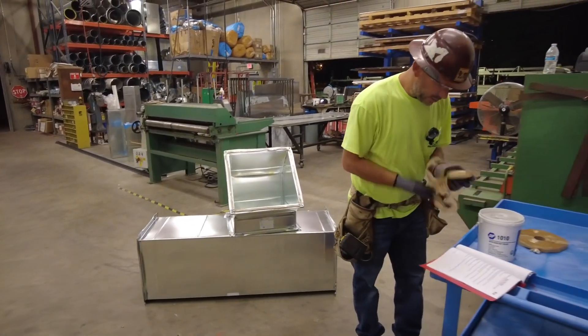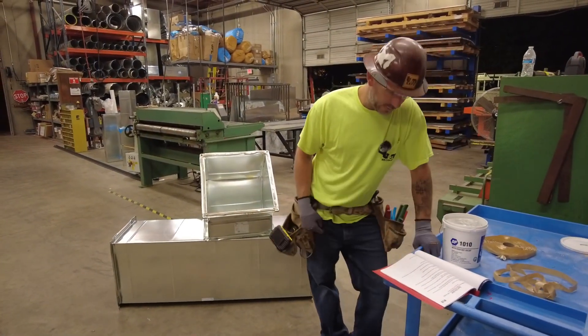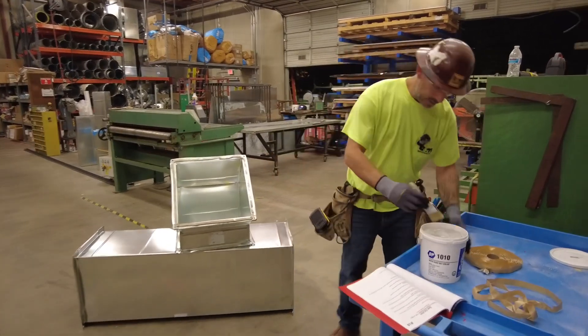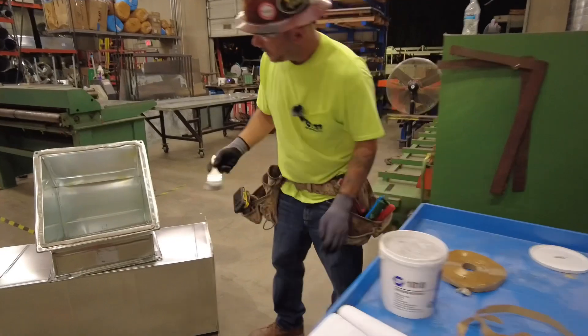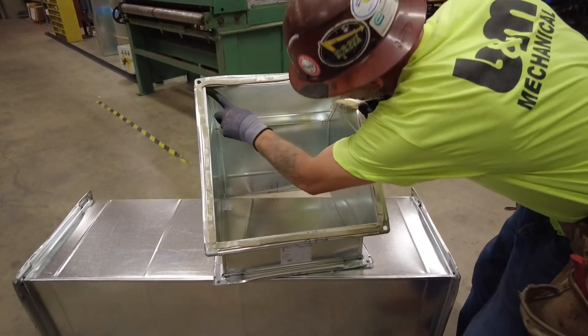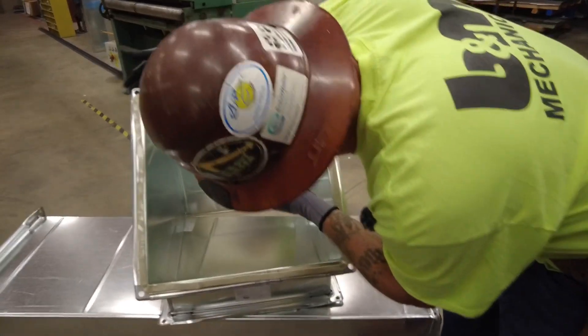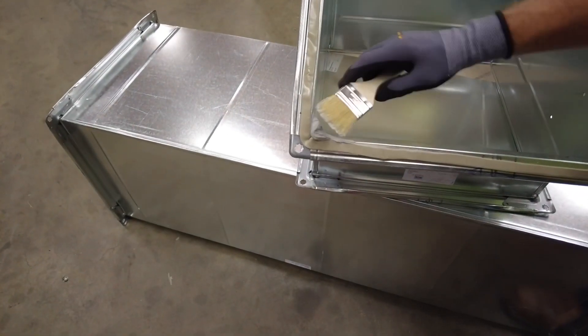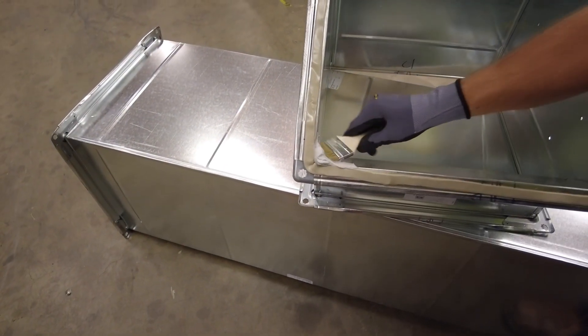Step four is to generously apply Pookie to each corner of the duct from the TDF approximately two inches down. There are holes in these corners, so you can see daylight through them. It's very important to go two inches down and have the Pookie built up a bit there for when the connecting duct comes in.